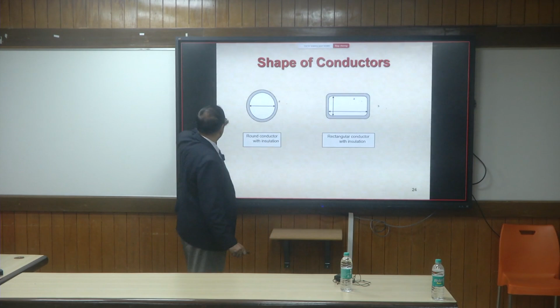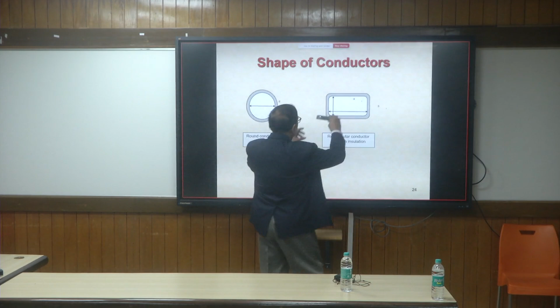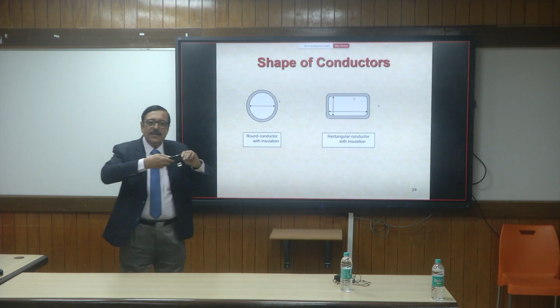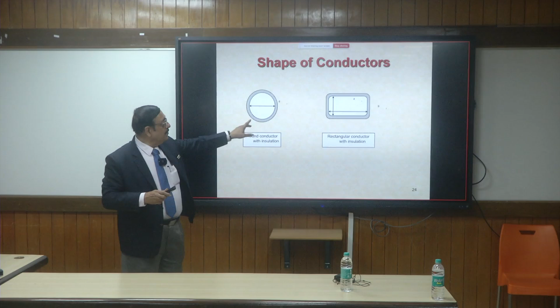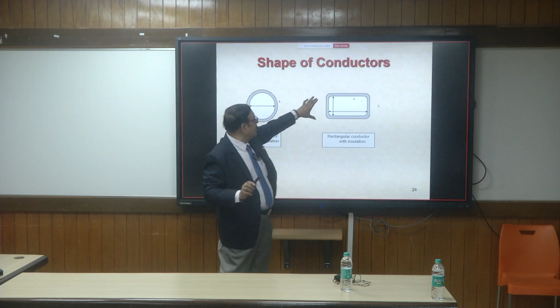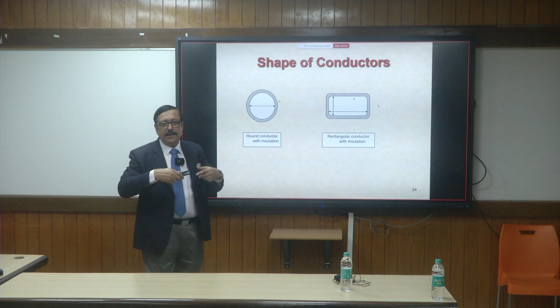The problem is, practically, if you have a very thin rectangular conductor, while winding, the wires will twist, and it doesn't make sense to maintain the rectangle, because this rectangle may be like this and the next one may stand up like that. So all the thin wires are invariably going to be round, because no matter how much you twist, the cross section remains round. So space utilization is there, and if you're thinking of bigger sizes, then only rectangular conductors are effective in implementation. In small size, it's not effective. I'd rather say below a few millimeters at least of width, rectangular conductors are not useful. Theoretically they can exist, but they are not useful, because by twisting of the wires while winding, you can't control it.